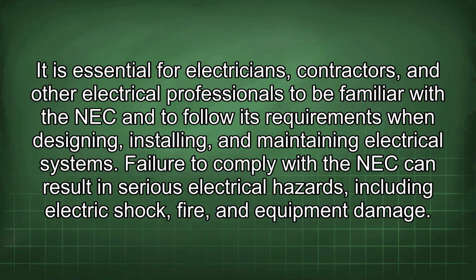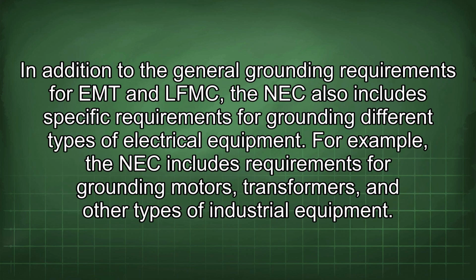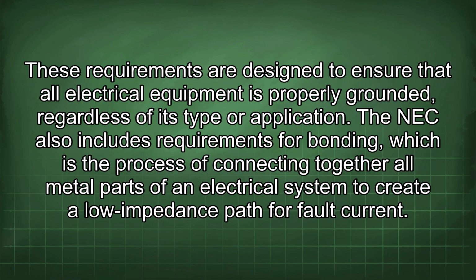Failure to comply with the NEC can result in serious electrical hazards, including electric shock, fire, and equipment damage. In addition to the general grounding requirements for EMT and LFMC, the NEC also includes specific requirements for grounding different types of electrical equipment. For example, the NEC includes requirements for grounding motors, transformers, and other types of industrial equipment. These requirements are designed to ensure that all electrical equipment is properly grounded, regardless of its type or application.